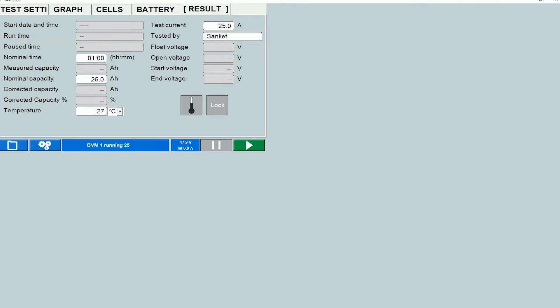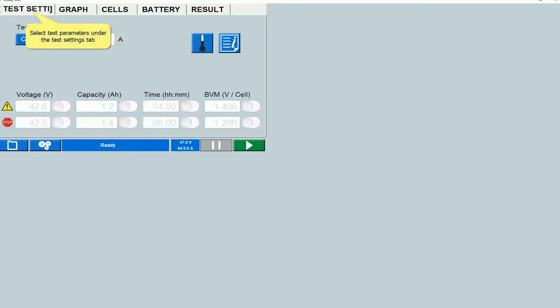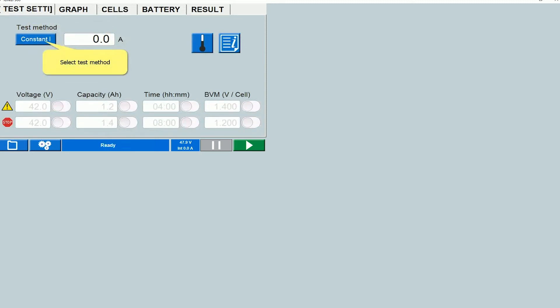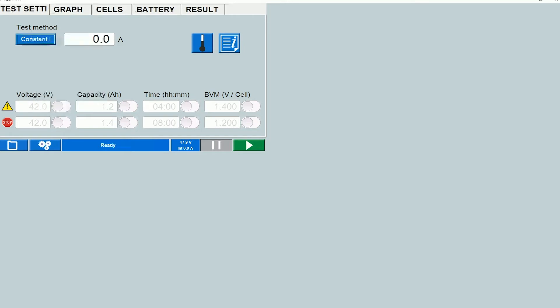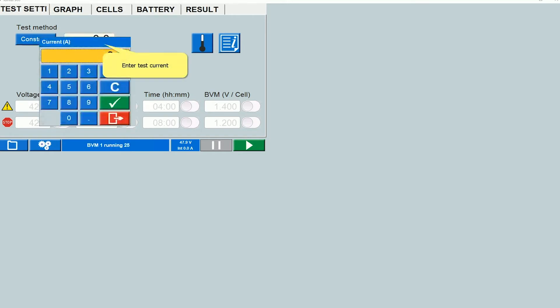Once you have entered information under the battery tab and the results tab you can switch over to the test settings tab and make changes over here. You can select the test method. There are all these different options. Typically you would do the constant current test. So let's stick with that for this video. You would enter the test current over here.